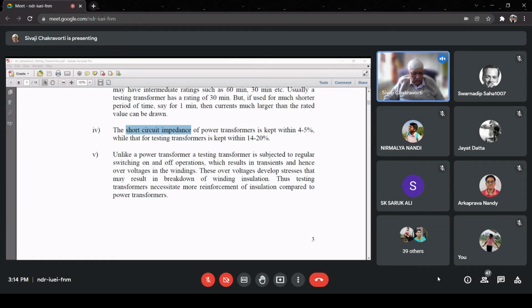This you must be able to say because you have studied probably last semester also. Impedance of a transformer when secondary is short circuited. Secondary short circuited. Yes, correct. But this is which impedance? Series impedance. Coming from what? Leakage impedance. Yes, that's a very good answer. Correct. This is basically the leakage impedance, because resistance is generally very low, so we have the leakage reactance. It is basically that leakage impedance of the transformer. That's called the short circuit impedance.